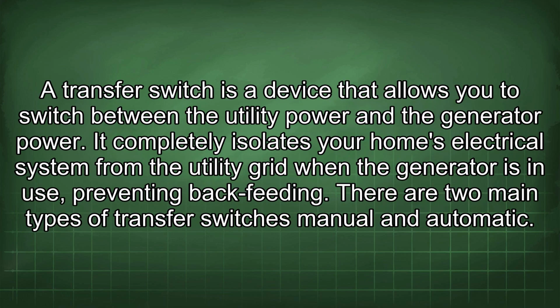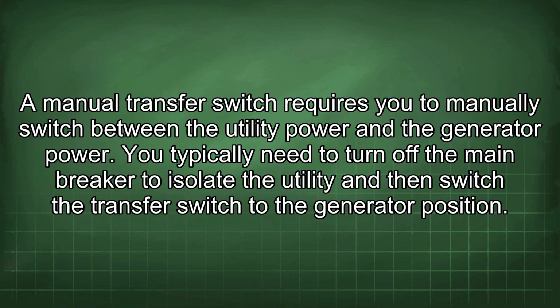A transfer switch is a device that allows you to switch between the utility power and the generator power. It completely isolates your home's electrical system from the utility grid when the generator is in use, preventing backfeeding. There are two main types of transfer switches: manual and automatic. A manual transfer switch requires you to manually switch between the utility power and the generator power.